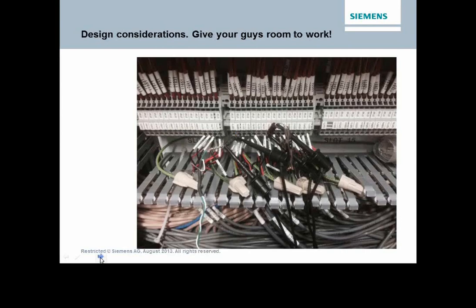The value of being able to hook up with the software in the marshalling panel is, in this case, on a cold winter day, instead of going to the top of a 50-foot silo or going into a process area that can be hazardous with vapors, whatever, I can actually have connections to the device, the unit's hygienic radar, right from the control room. We can also get set up with HART multiplexers, so that with the software you can actually interrogate and take a look at a device or a number of devices simultaneously.